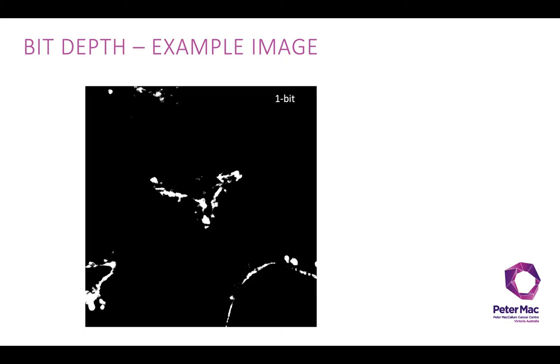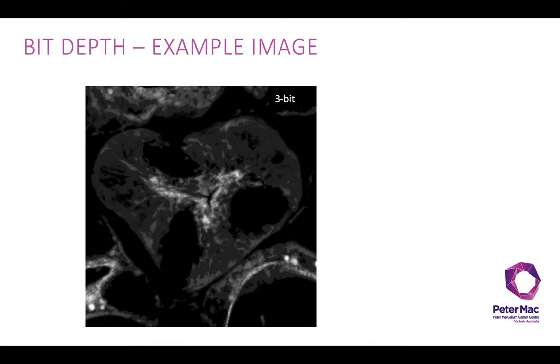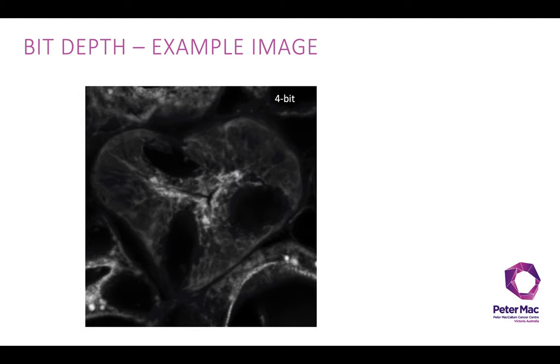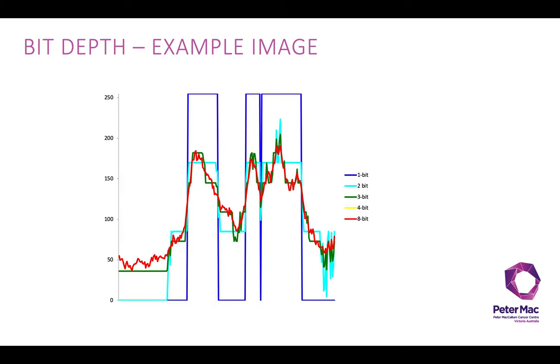Here's a microscope image example. A 1-bit image is either black or white — there's not very much information. But as we go up through the bit depth ranges, there's much more information. If we do some simple quantitative analysis — a line analysis — we can look at the intensity along that line. On the 1-bit scale, we've got either 0 or 255 grayscale values. As we go up in bit depth, we get much more information about the intensities across that line.